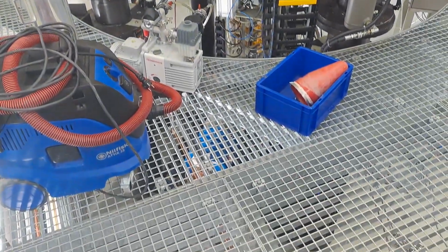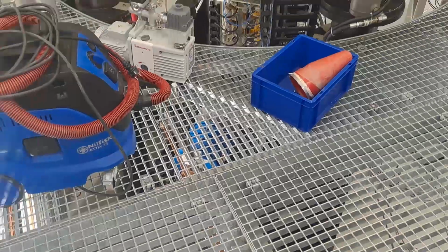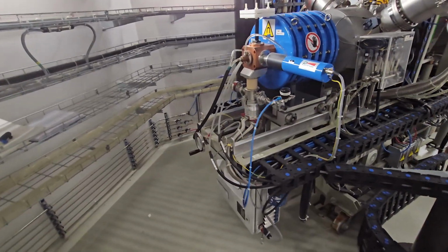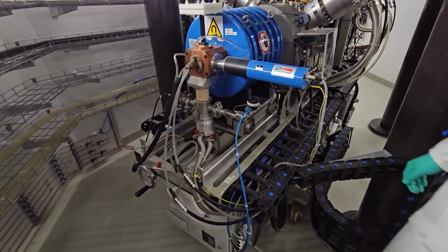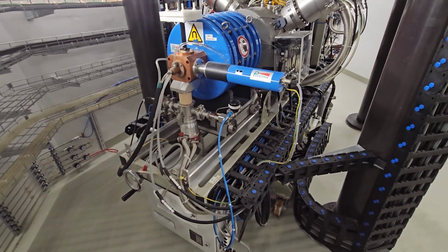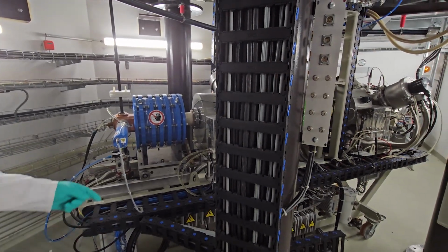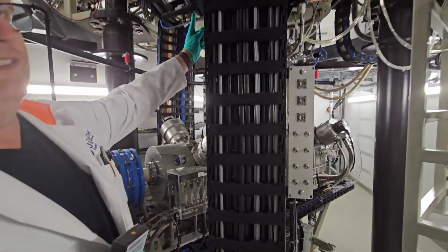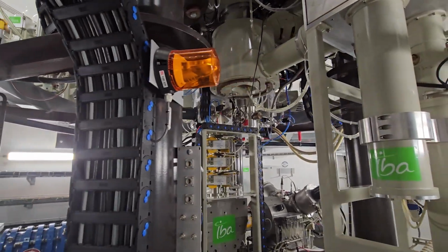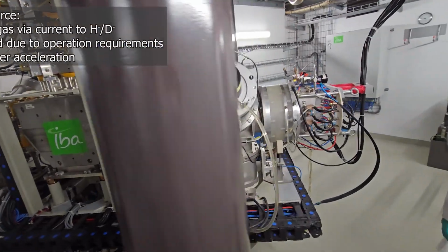This blue component is the alpha ion source. A closer look shows that helium gas is injected and fully ionized here. It's a plasma ion source. The helium ions are then transported via the beamline up into the cyclotron, located at the moment just above us. And then they can be accelerated.